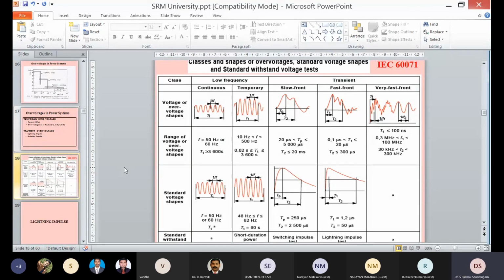So this is the waveform classification given by IEC 60071. IEC 60071 is the internationally accepted standard for insulation coordination definitions as well as impulse levels. Here they have given what the low frequency faults are and what the transients are. Under the transient, of course, switching impulse will come, lightning impulse will come, and very fast transients, that is gas insulated substation faults, also come under transients.